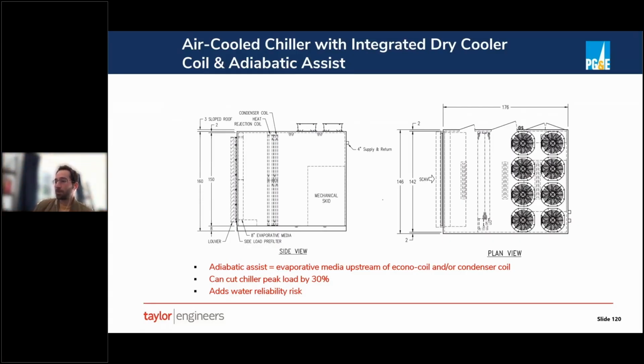There are a couple of benefits to this. One is obviously the energy efficiency benefit of that, right? You're increasing the amount of free cooling hours you have, which is great. But there's also potentially a first cost benefit. That's perhaps not intuitive because you're adding more components to the system, but you are significantly decreasing electrical load at design. And that's because even under design condition, when you perhaps can't do any free cooling, you are reducing the entering air temperature that the condenser coil sees.